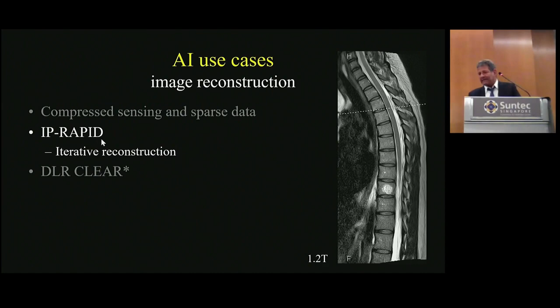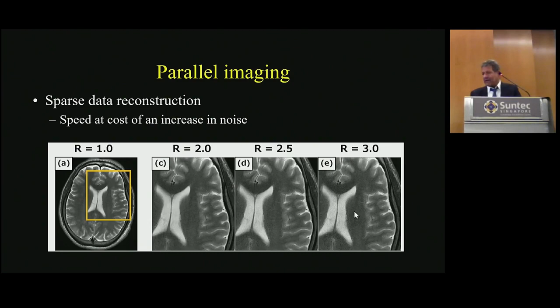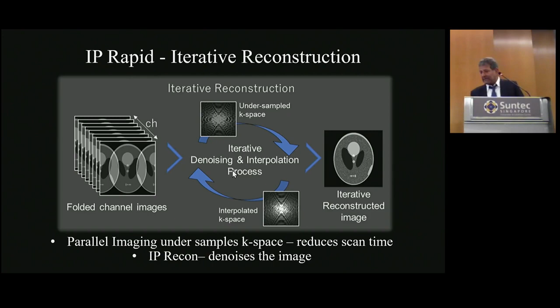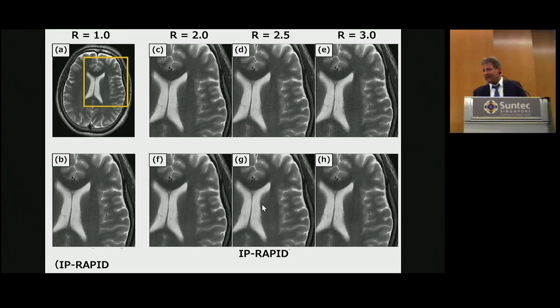process. And we do iterative reconstruction because it helps us recover some of the signal that we lose when we do parallel imaging. As you can see here, as we go to higher parallel imaging factors, the image integrity is still maintained, but we start to get noise. We can use this iterative reconstruction process, which not only cleans up the aliasing, but also cleans up the noise, to get an image that maintains the signal that we expect. Here you see the top line without deep learning reconstruction. Here you can see, actually without AI reconstruction, IP Rapid isn't strictly deep learning. You can see that it actually maintains the signal very nicely. So the iterative reconstruction piece does a very nice job at improving signal to noise.